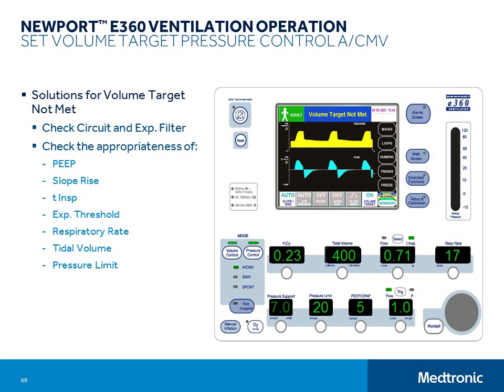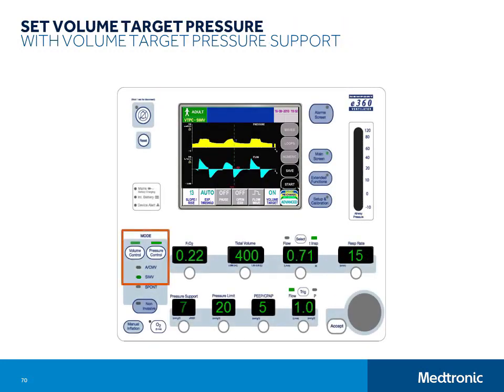When you change to volume target pressure control SIMV, both the mandatory pressure controlled breaths and the spontaneous pressure support breaths are volume targeted breaths that are delivered at the lowest possible pressure. You will notice that the pressure support setting is dimmed. That's because the pressure support setting does not manage the pressure support level in this breath type. Instead, it is managed by the ventilator, and the ventilator uses the pressure limit setting to determine the maximum pressure it will use for all breaths, both mandatory and spontaneous. The peak pressure for the mandatory breaths may be different than the peak pressures of the spontaneous breaths, because mandatory and spontaneous breaths are handled individually. The inspiratory time setting determines the duration for the mandatory breaths, and the expiratory threshold setting determines the duration for the spontaneous breaths. The slope rise setting applies to both the mandatory and spontaneous breaths.